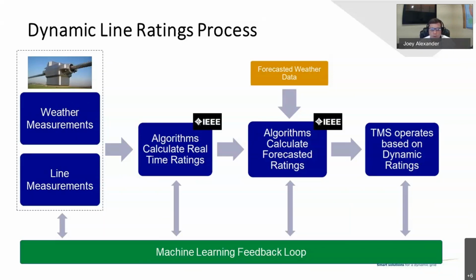So using our vibration metrology that I mentioned before, we're able to translate vibration into wind speed. As that perpendicular wind blows across the line, it has a very specific signature in the vibration spectrum, and we use fancy fluid dynamic models to accurately translate that into the real wind speed hitting that line.